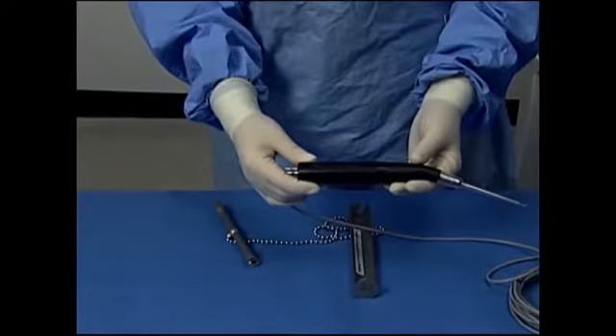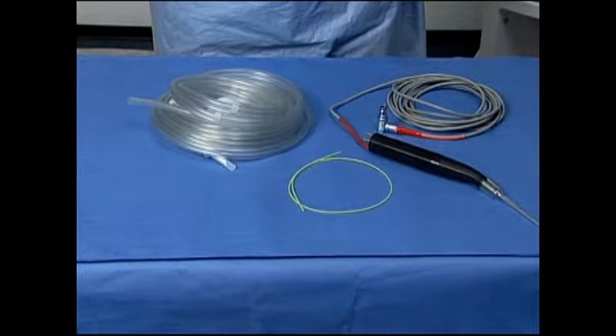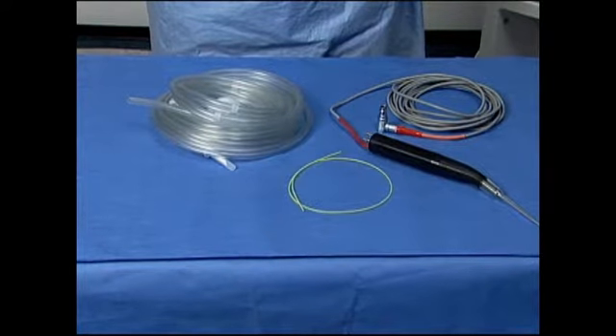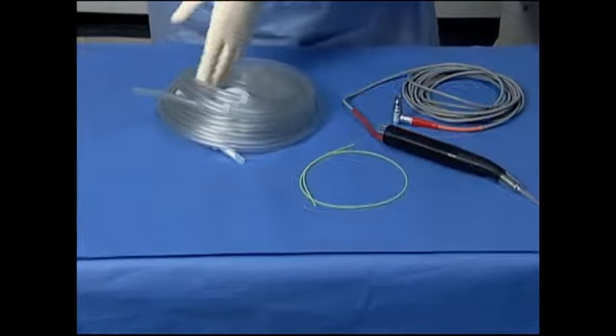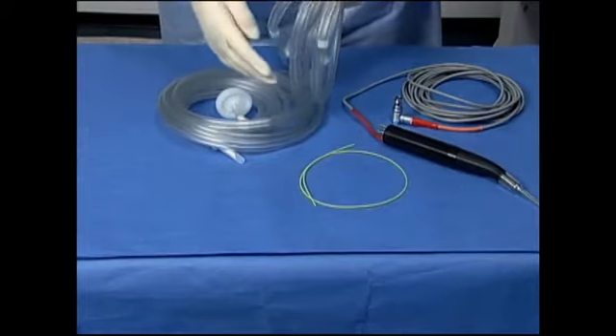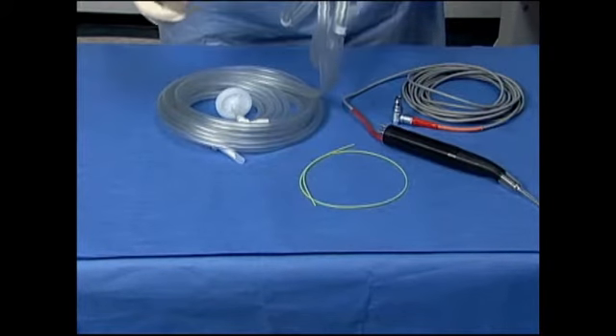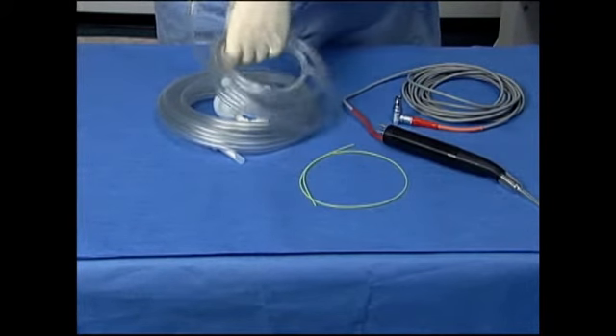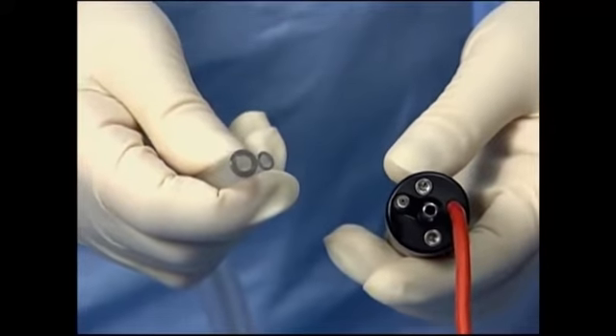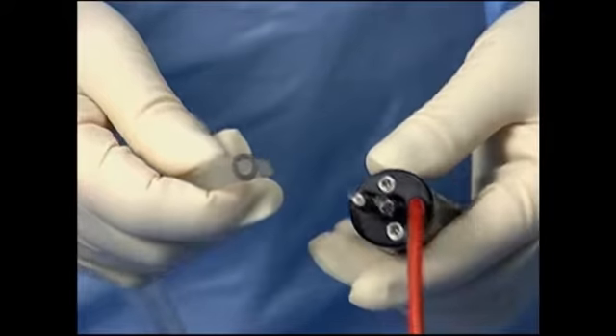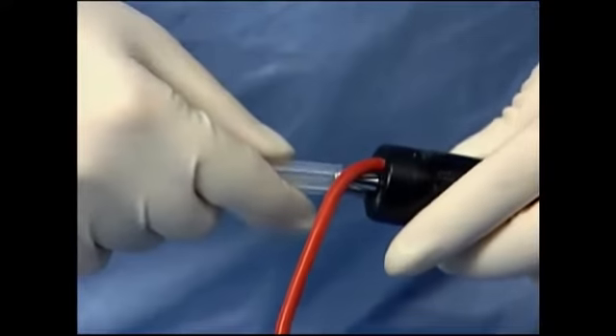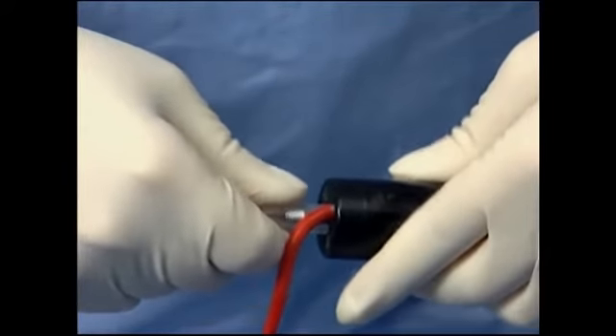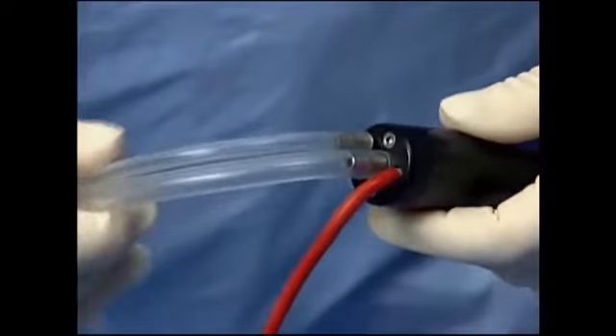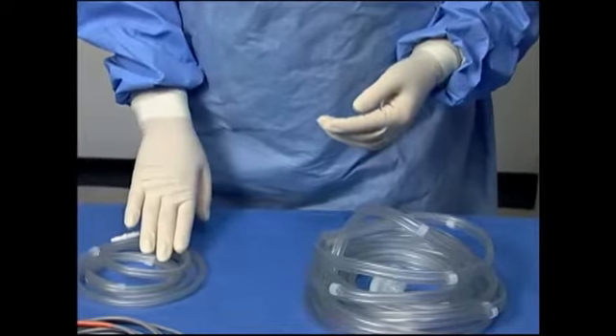The tubing kit contains a sterile tubing kit, hose clips, and stylet. Open the kit, remove the tubing kit from the wrapper, and turn the tubing kit over onto the sterile field. Locate the double lumen tubing from the center of the sterile tubing kit and connect it to the irrigation and aspiration ports on the back of the handpiece. If using the 24 kHz microsurgical handpiece, you will need the mini tubing kit.